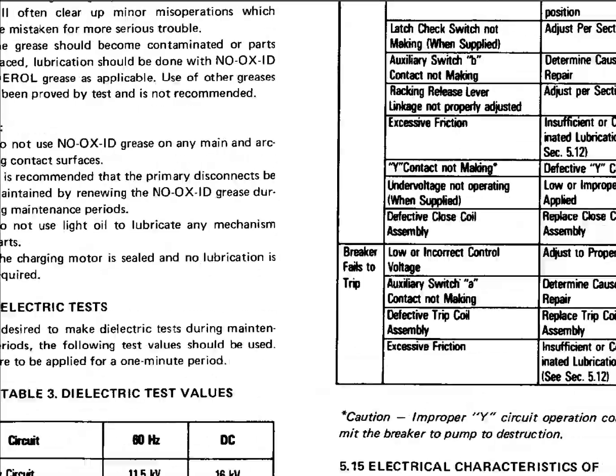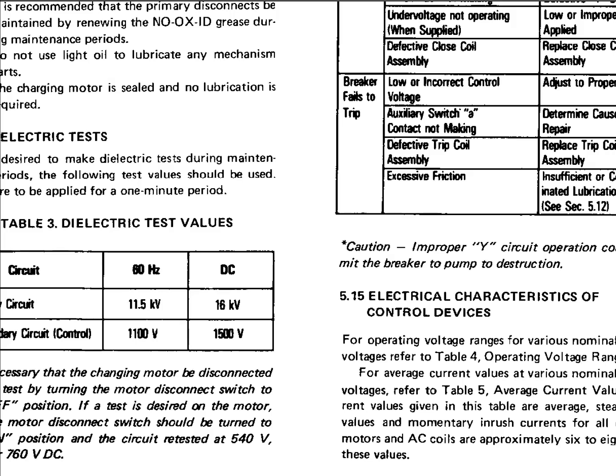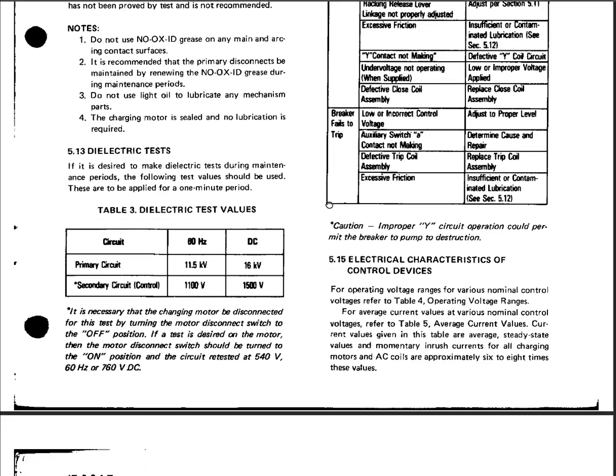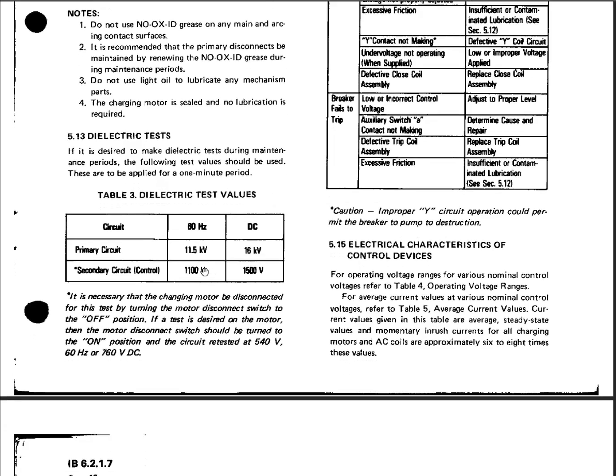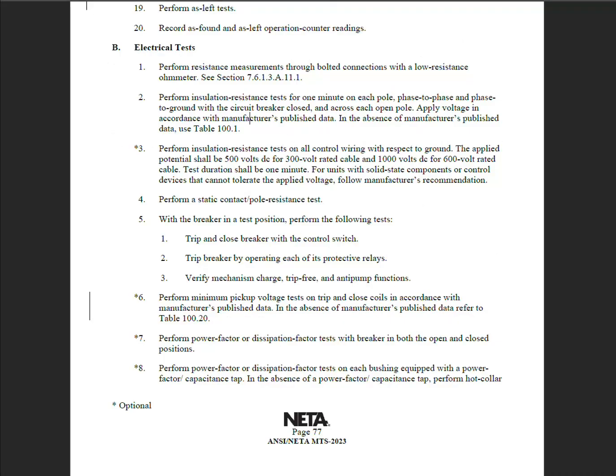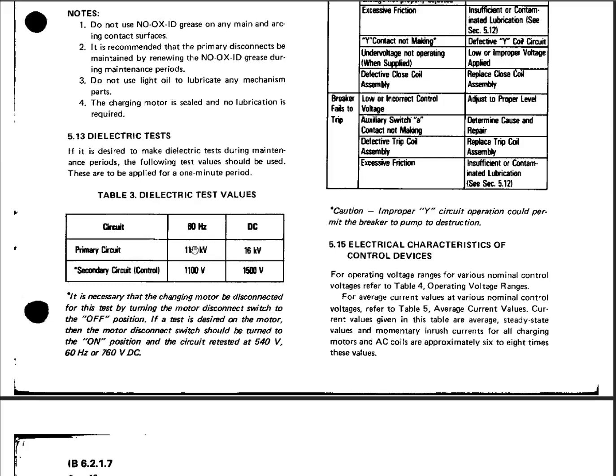So the high pot is nothing about insulation resistance. It says dielectric test values, right? That's usually a high pot test, but the problem is we don't have anything for a megger. So there you have your 60 hertz or your DC. If you look at these numbers and compare them to the MTS high pot tables, what you're going to find is they're not the same.